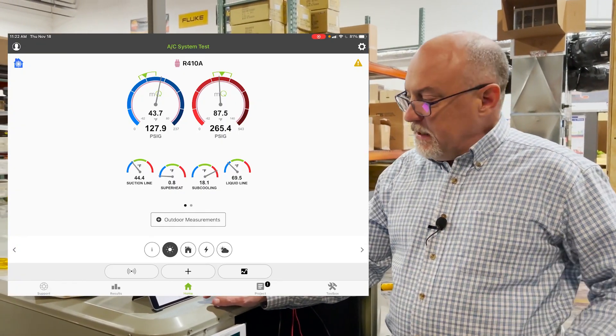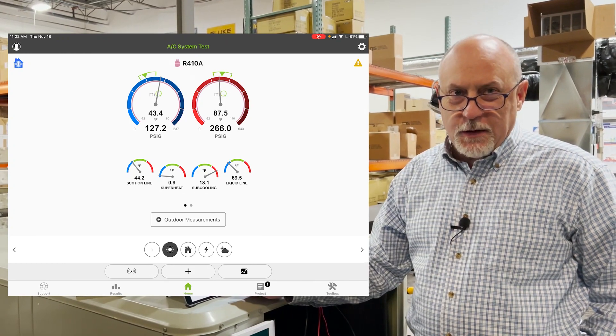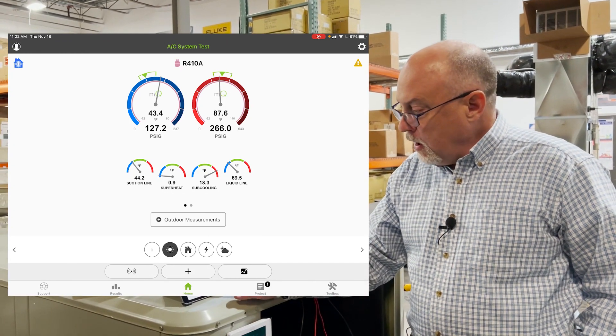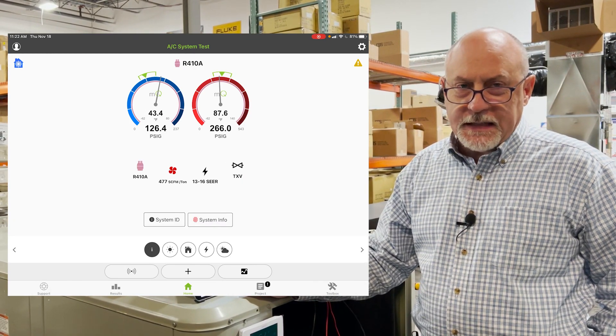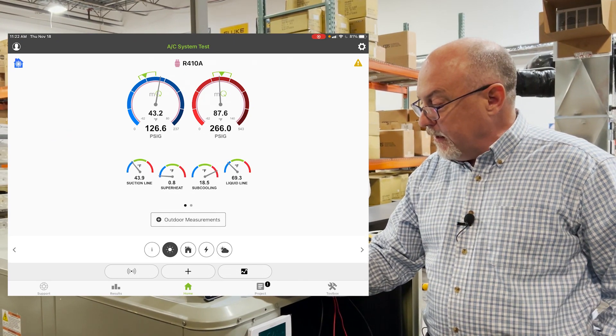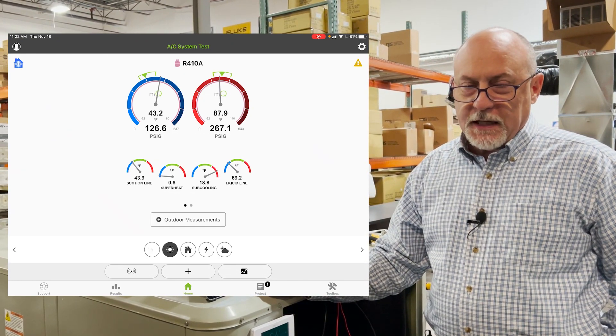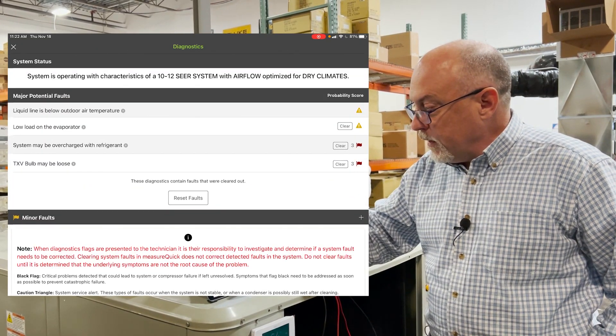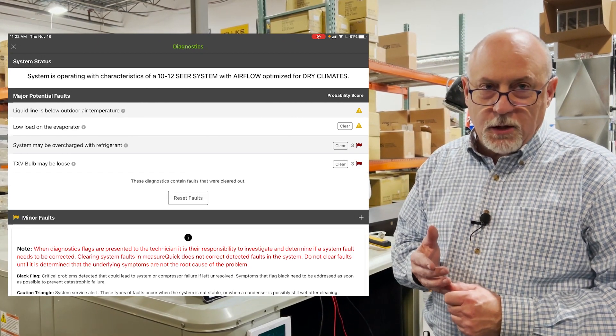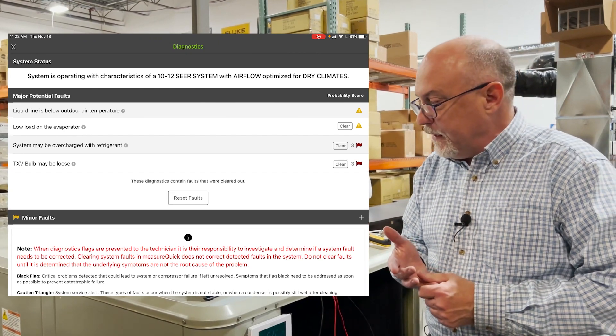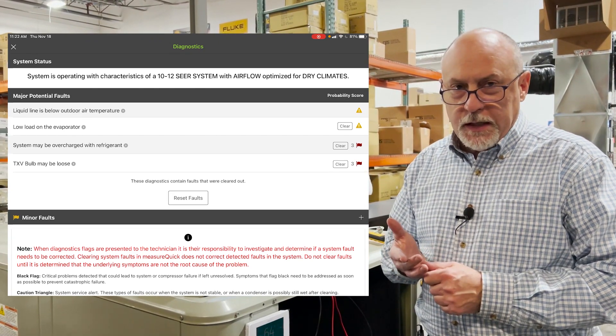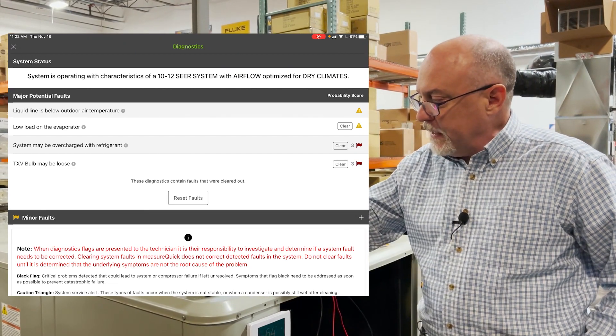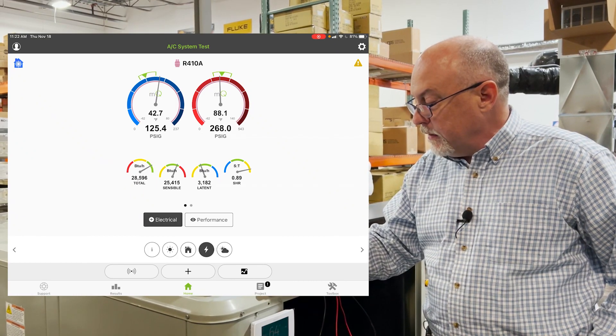All right, so the system stabilized a little bit, and you can see right from the factory we're running about 18 degrees of sub-cooling. So the system is a little bit overcharged. Also, we don't have a duct system on here, so we're moving about 477 CFM per ton. And if you take a look at the superheat on here, it's running about 8 tenths. So I'm sure MeasureQuick's picking up that it could have a loose TXV bulb effect. Let's just take a look here. We got liquid line temperature's low, and that's because we're stacking liquid in the condenser. We've got low load on the evaporator, cooling the shop in here. System may be overcharged, high sub-cooling, and we have that really low superheat. So we do need to go through and check a couple other things here. But while we're here, I'm just going to get electrical measurements now on the condenser.